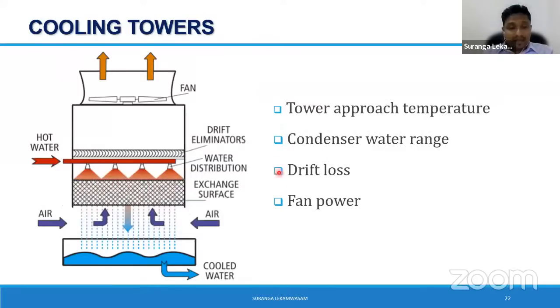Then quickly, I will touch the cooling tower. That is the heat dissipating element in the system. So you supply hot water through this spreader. The water drips downward through this infill, which is a honeycomb structure made that way to increase the contact area where you blow air upward. So then you can see air and water contact.